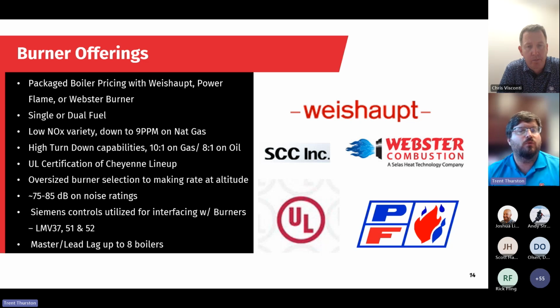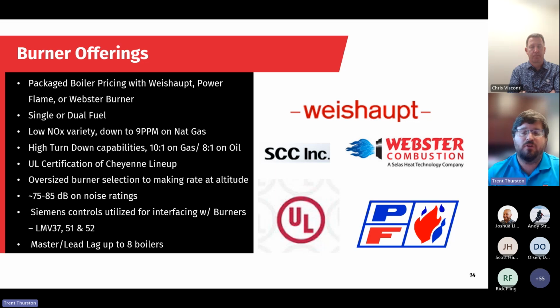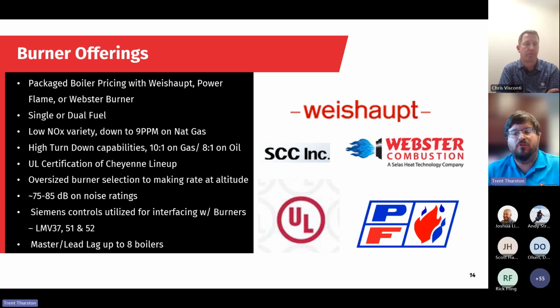One of the things that we can do, since we're flexible with the burner package, is that we can oversize the burner selection to make rate at altitude. There are some trade-offs with this. We lose some turndown, but we'll still be a minimum of 4-to-1, and a larger burner will cost more, but it still will make rate at altitude, even at potentially up to 7,000 feet or higher. The other thing that we have is we use Siemens standardized controls. So the burner control interface will be a Siemens, and this is very helpful to integrate with our Siemens lead-lag panel, or we can work with a customer-furnished BMS if required.